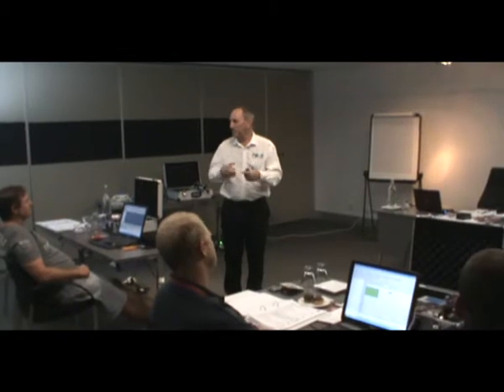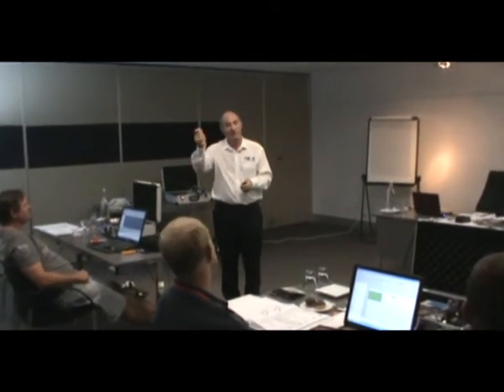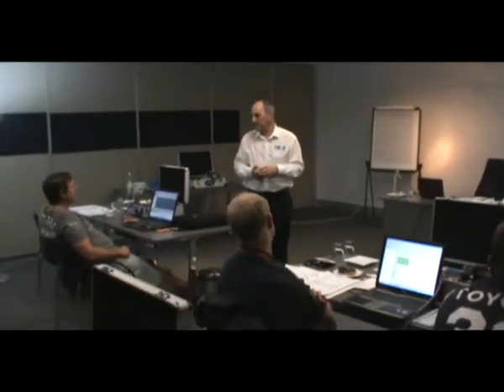They commission the system, it works perfectly, they get really good performance, but then a couple of months down the line, an IT guy comes along and he says, oh, I want to put a modem in that cabinet. It needs 24 volts. Where do I get 24 volts from? It's a 24 volt power supply there. So he hooks up to the power supply. The power supply is now delivering not 4 amps but 4.5 amps. It still works, of course, because it's less than the 5 amp current that the device can deliver.